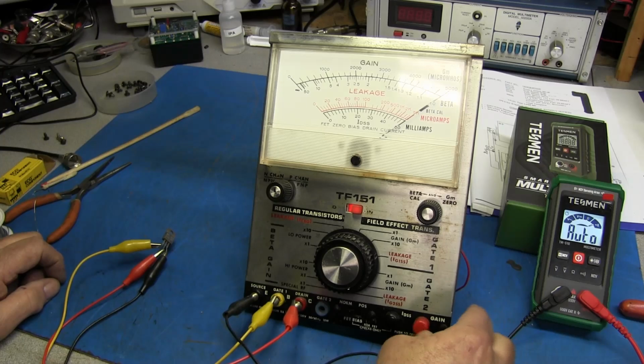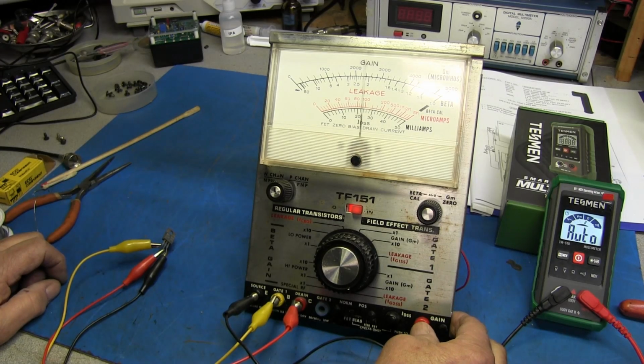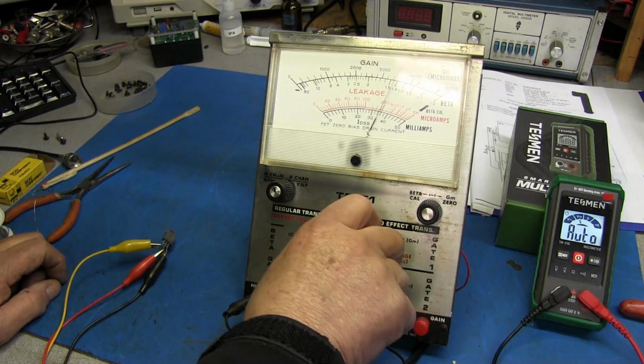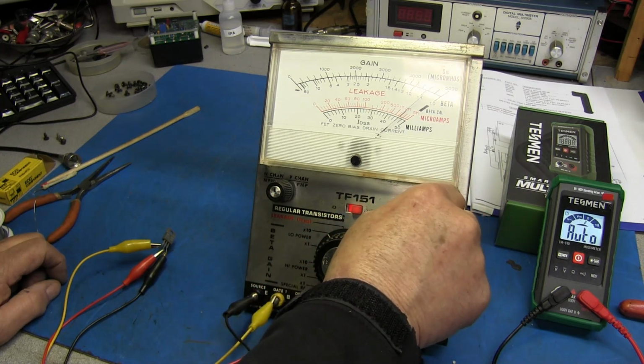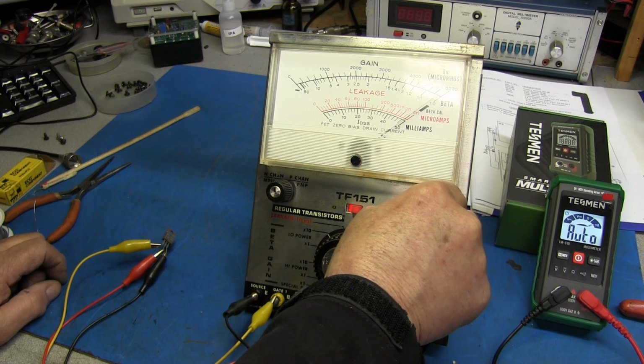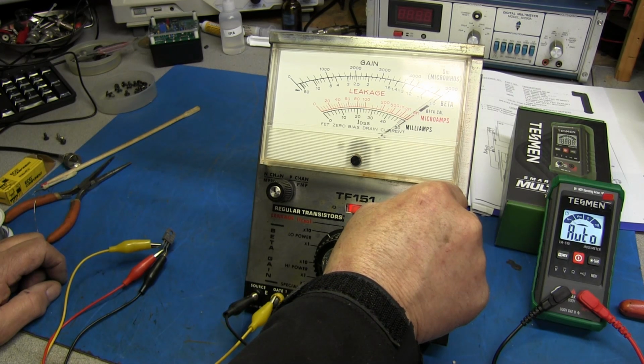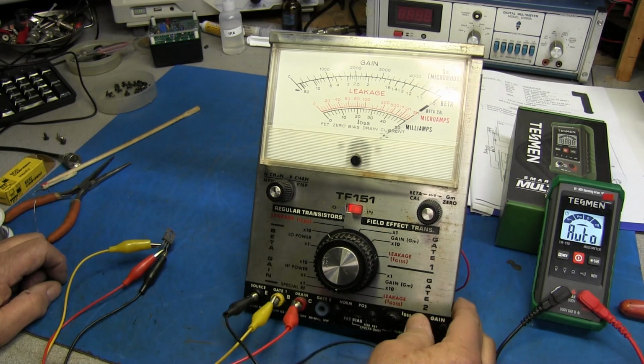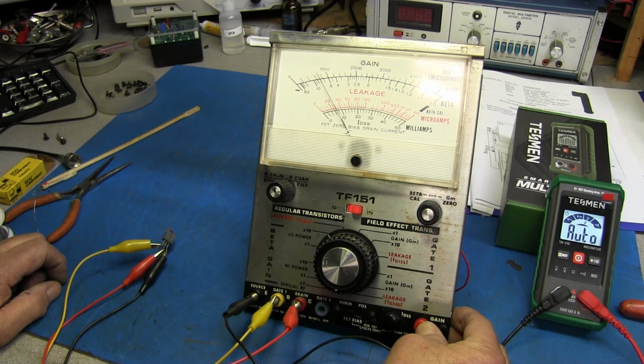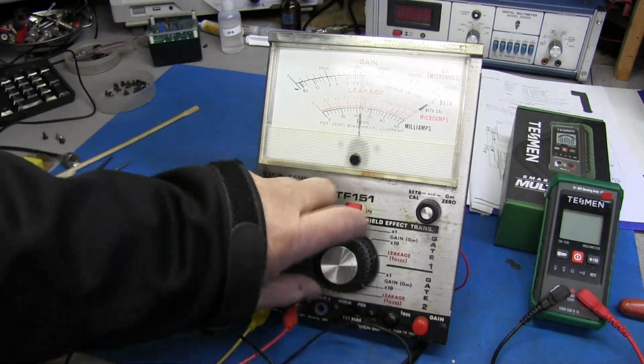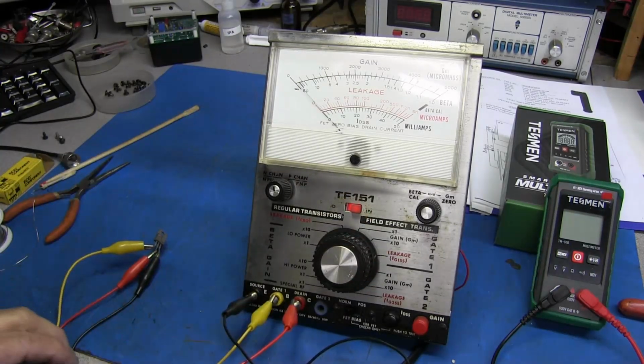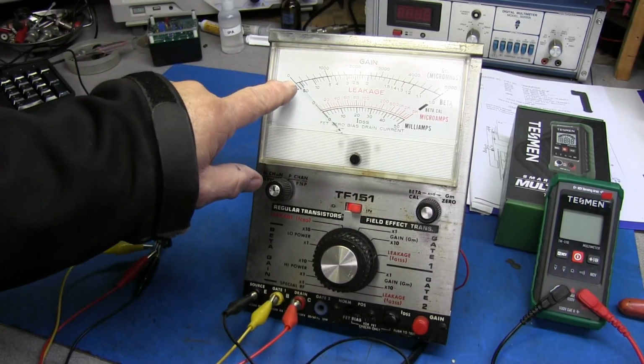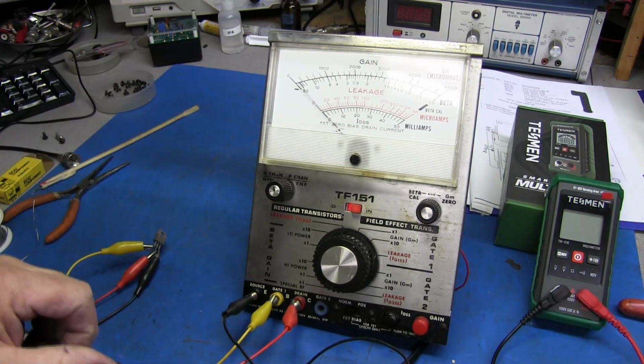We'll set that to beta cal. Press the gain. It's about a 49. We'll go to high. Recalibrate. That part's very touchy, needs cleaning. Gain looks about 850 on it. We go down to the leakage test. We got just a little move of the needle up, so the leakage looks good.